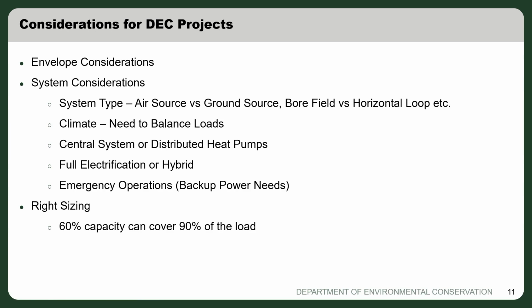Right sizing is very important, as I touched on before. Often we find that an electrified system designed for 60% of the capacity will actually handle about 90% of your needs. The cost of bore fields, trenching, and systems is so expensive it might kill the economics of the project. So if you right size the systems and accept that, say, 10% of the time you'll have to use hydronic or a ModCon system, that's better than not doing the project at all because you couldn't afford it.